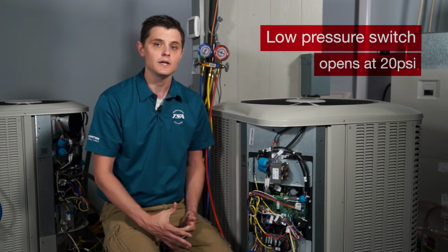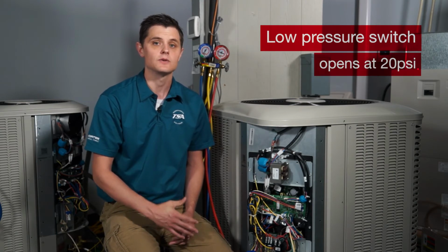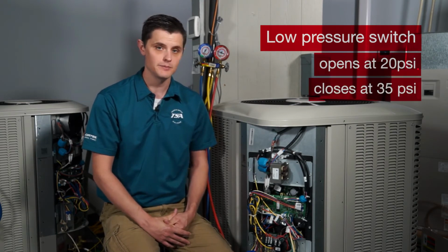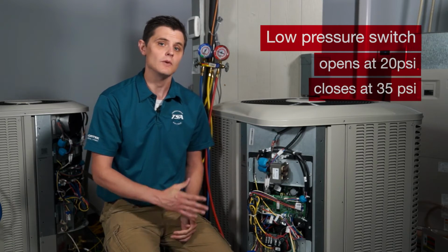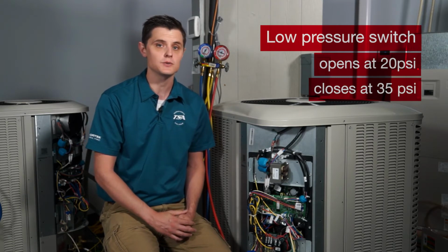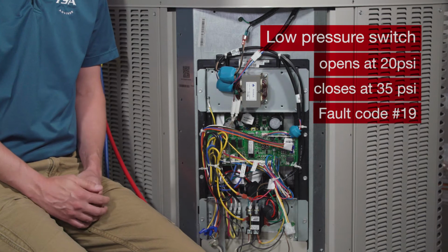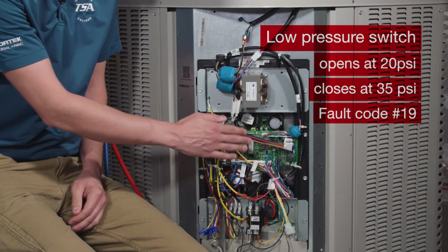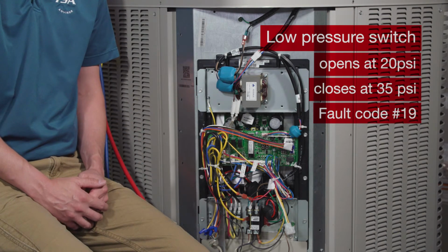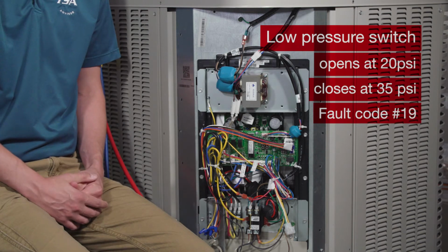The low pressure switch is going to open at 20 PSI, and then it's going to reclose at 35 PSI. Anytime that you get a low pressure switch fault code, it's going to be a number 19, which will be displayed on your interface board. And that is going to be the low pressure switch.